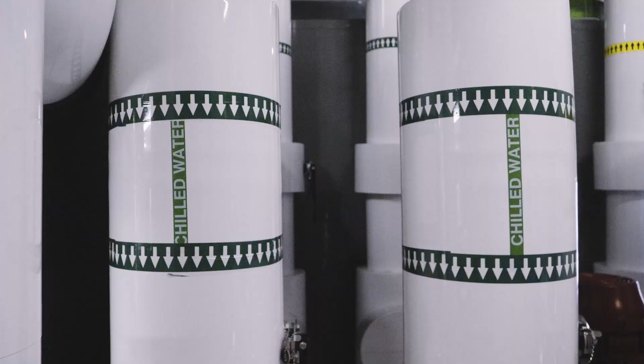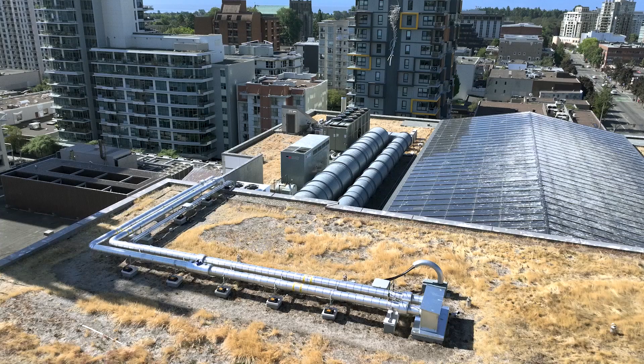I think the only real surprise we had with this project was some of the performance data of the equipment being a little overstated when it's being sold. While it says it can do it on paper, that doesn't necessarily mean it can do it 24 hours a day, 7 days a week. The original design had anticipated a bit of a lower friction loss in the pipes than was proving to be the actual fact. So initially we anticipated the pumps to run around 50 to 60%, but in the end we had to ramp them up much closer to around 90% or so. I guess the lesson learned is to make sure you don't purchase your pumps just big enough—give yourself a little wiggle room on the upper end.